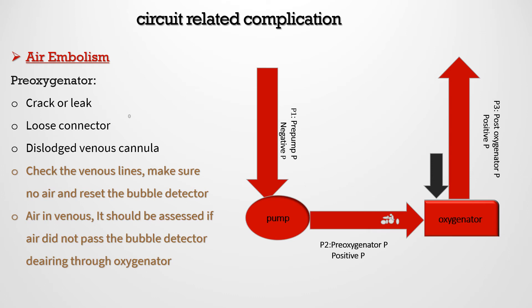Another ECMO circuit complication is air embolism, one of the most life-threatening complications. If air is detected inside the circuit, clamp the return line immediately. Pre-oxygenator air may be due to improper priming, a leak or crack in the circuit, loose connections between the venous cannula and circuit tubing, or malposition of the venous cannula. Check the venous line, ensure there is no air, and reset the bubble detector. If a small amount of air is present in the venous line and has not passed the bubble detector, it can be aspirated from the pre-oxygenator port and de-aired through the oxygenator.